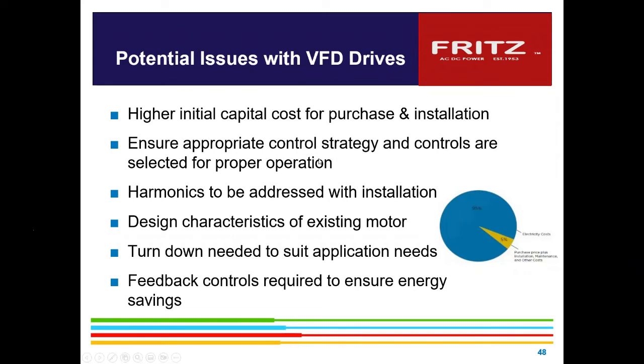Make sure you've got the proper control strategy in your control systems. Harmonics, which, if you want to join me on the second, I'll go into in more and more detail, so that you consider not only the input noise factors but the output noise factors. It's more on applications where you have multiple drives. A small number of drives isn't a real problem, but if you're putting all these on, that's back to that pulsing that goes into the drive and then the pulsing that goes out.